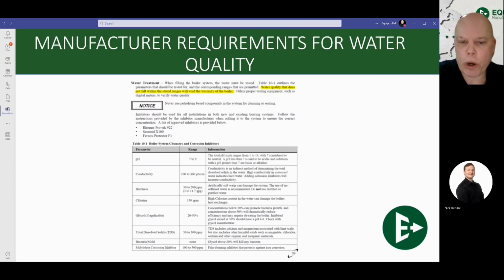A note here: this is one of the installation manuals from a boiler. Doesn't matter whose, but it shows how the installation manual details what the water quality must be in our systems. In this case, you can see the pH of this particular boiler must be between 7 and 9. Your hardness between 50 and 200 parts per million, or 3 to 11 grains per gallon. Chlorine, 150 parts per million. Glycol, 50% maximum. TDS, or total dissolved solids, 300 parts per million.